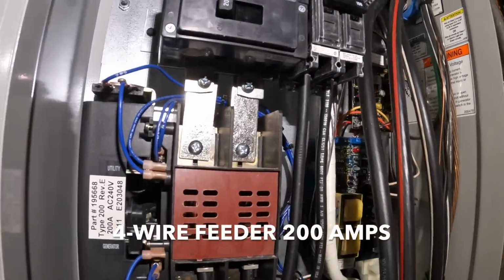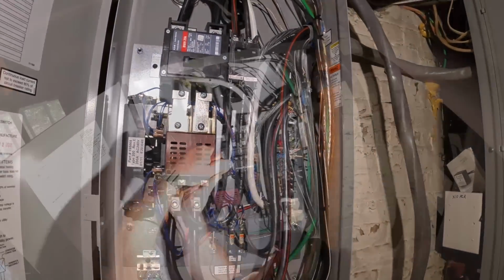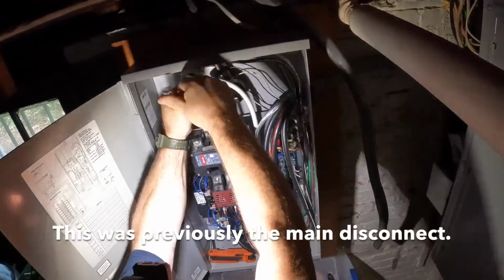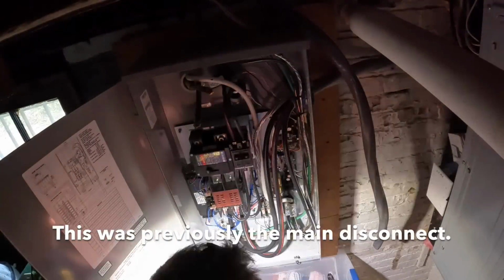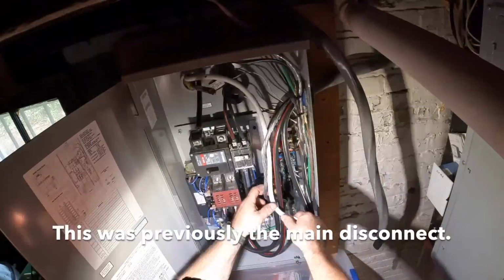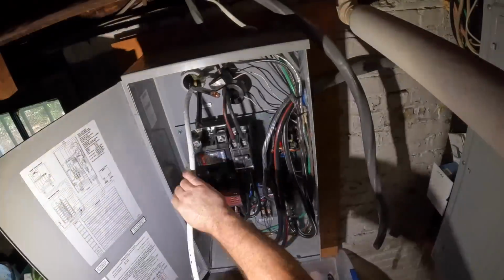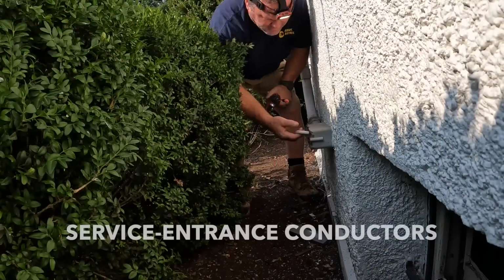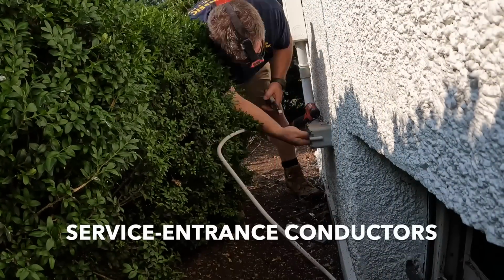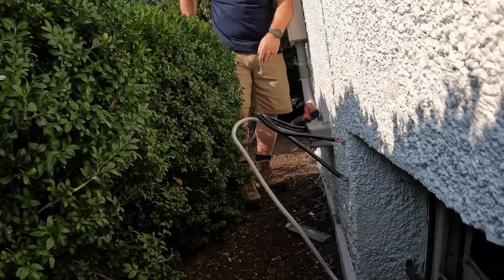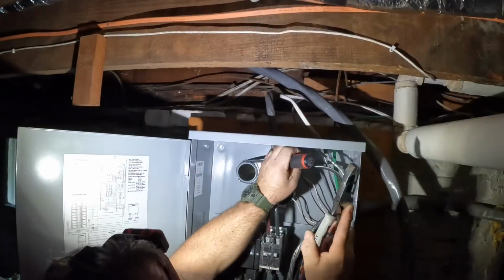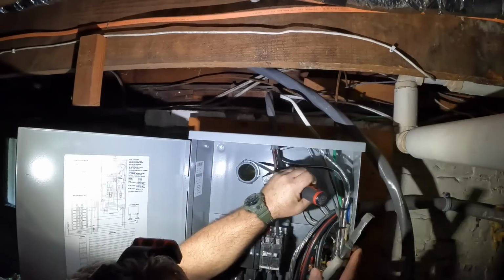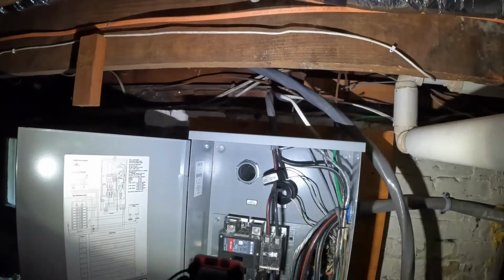So that's the anatomy of what we're doing today. This is a service-rated automatic transfer switch, so naturally all of our grounding and bonding takes place here. We ran new grounding electrode conductors and installed new grounding electrodes at the new service disconnect installed in the previous video. Existing grounding electrodes were disconnected after the new service was energized.